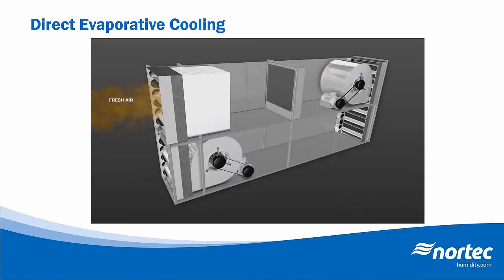The first one that we'll look at is a direct evaporative cooling system. This is probably the most common form of evaporative cooling strategy. In this case, the humidifier adds moisture directly to the incoming airstream, raising its humidity and reducing its temperature. Here, 100% fresh air is used, but warmer return air from the space can be mixed with outside air upstream of the evaporative cooler as well. The advantage of this strategy is that 100% of the cooling effect is felt by the room. But a disadvantage is that the amount of cooling that we can achieve using direct evaporative cooling is highly dependent on the supply air condition or the incoming air. Air that has a high level of humidity already will not be able to absorb as much moisture, reducing the overall cooling potential.